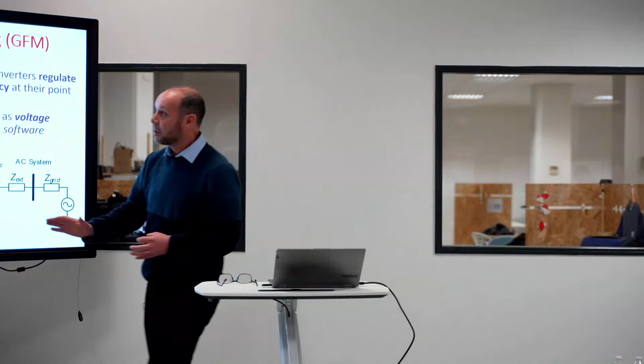We have two systems: grid following and grid forming. Any inverter connected to the grid has to be controlled either through grid following or grid forming. In grid following, you are controlling the power and the current, using the inverter-based resource acting as a current source inverter. Whereas in grid forming, it acts as a voltage source inverter.